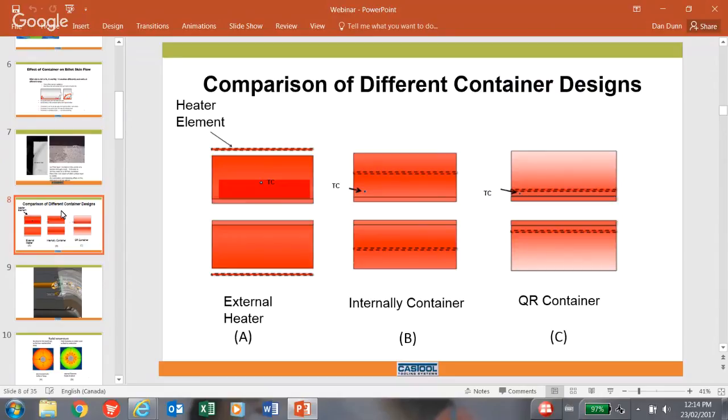Second to this, the elements are located on the OD of the body, which will not allow for adequate heat dissipation through the material to the atmosphere, allowing the body to radiate heat effectively. Also in this configuration, the container housing is heated, which has a negative effect on physical alignment as well as side cylinders and rods. Typically, supplementary air cooling on the container liner is used to control any overshoot of liner temperature.